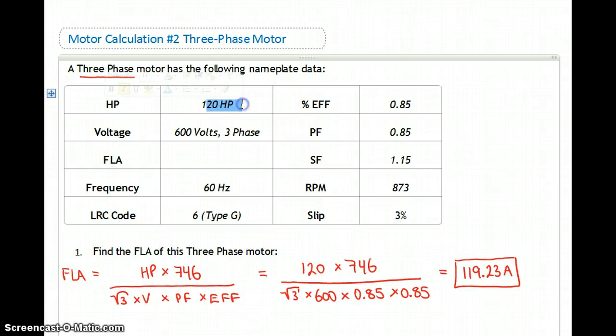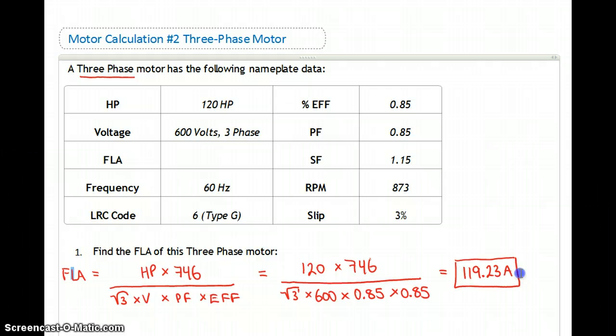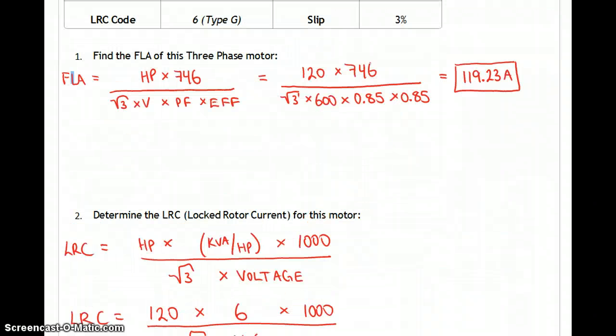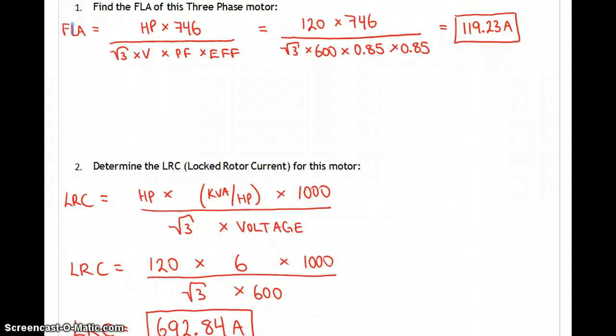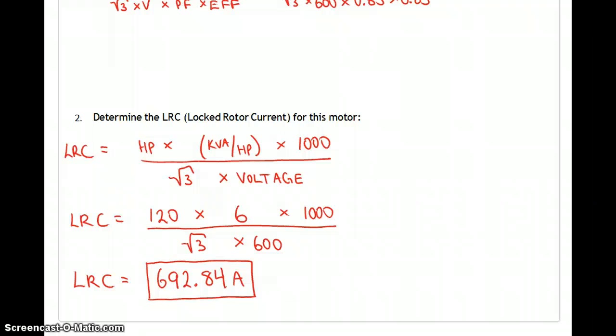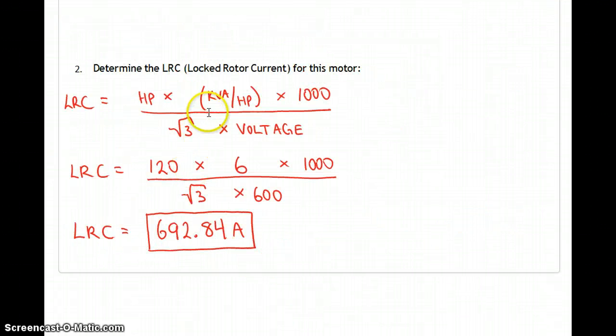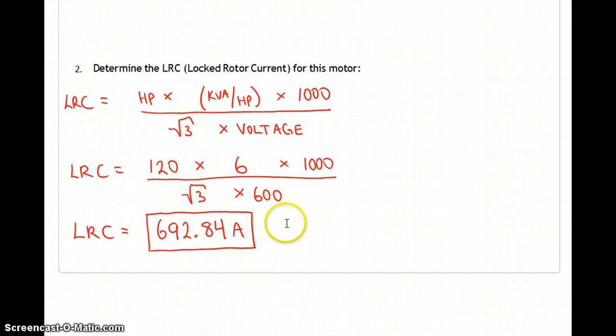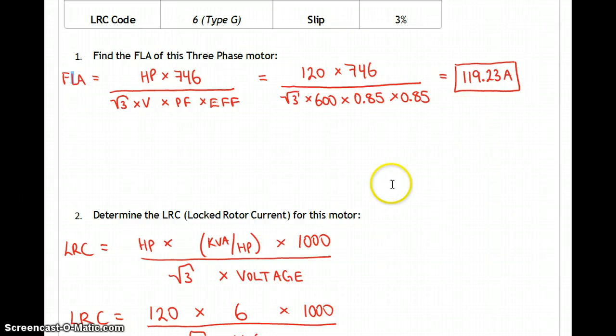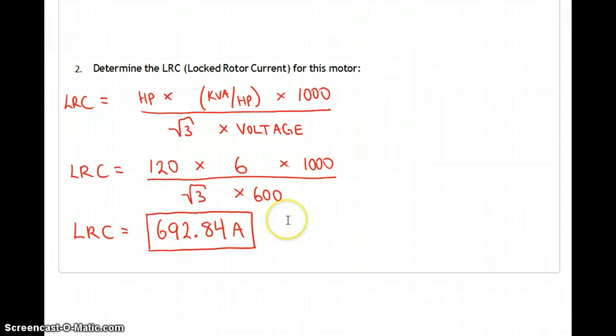At 600 volts, the full load current is roughly equal to the horsepower — 119.23 amps is very close to 120 horse. For locked rotor current: normally it pulls 119.23 amps, but when starting it pulls 692.84 amps. The formula is horsepower times kVA per horsepower times 1,000 over root 3 times voltage. That's the three-phase version — running current is close to 120 amps, starting current is six times that at 693 amps.